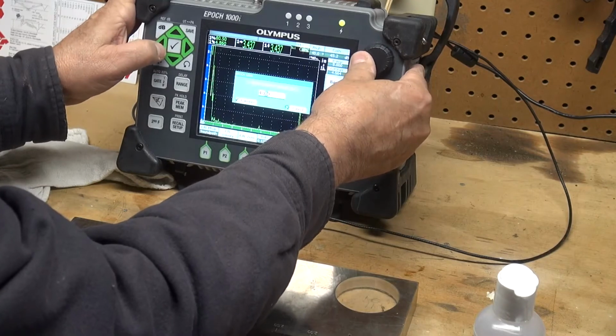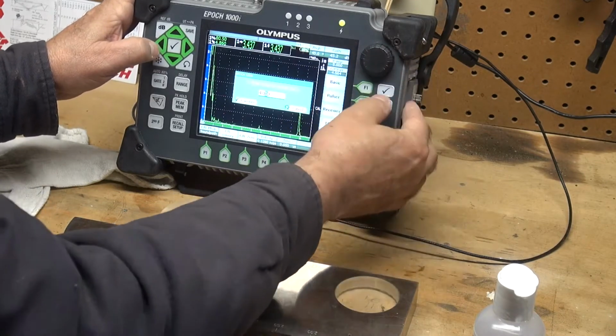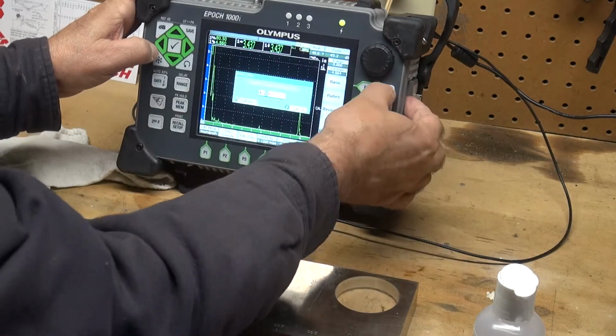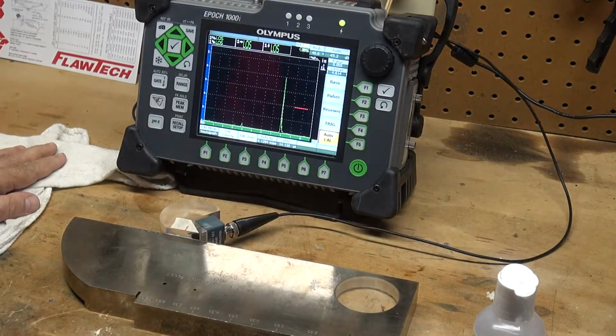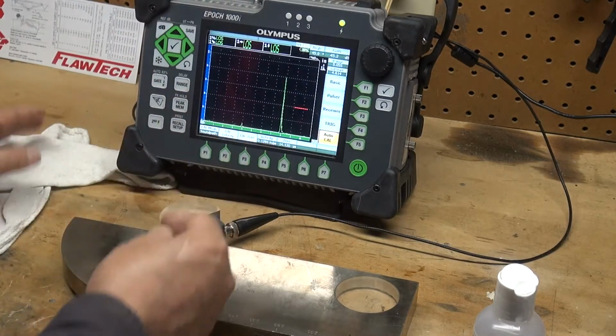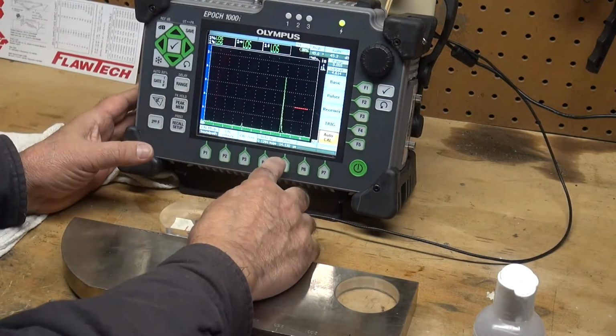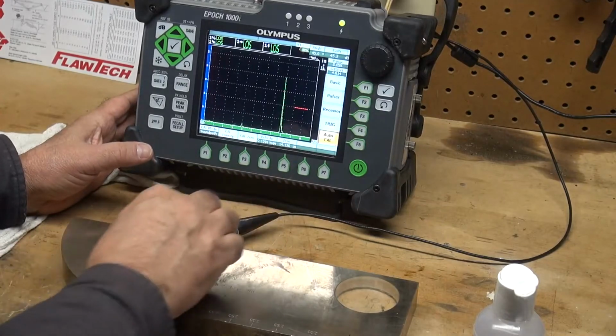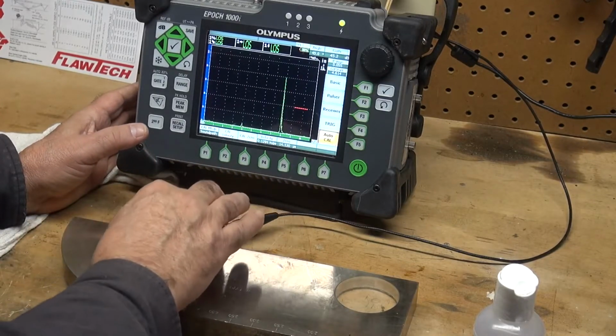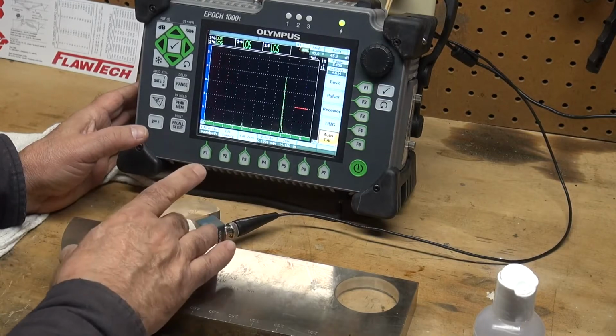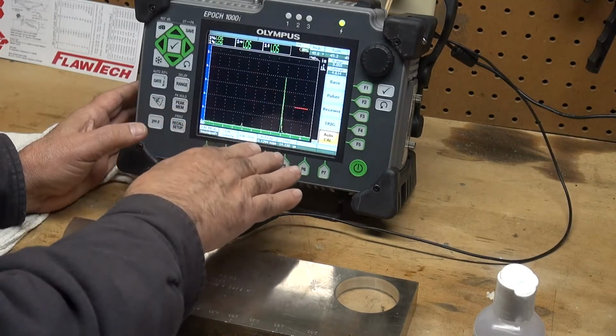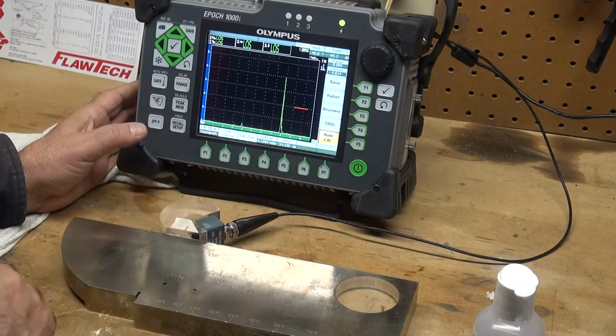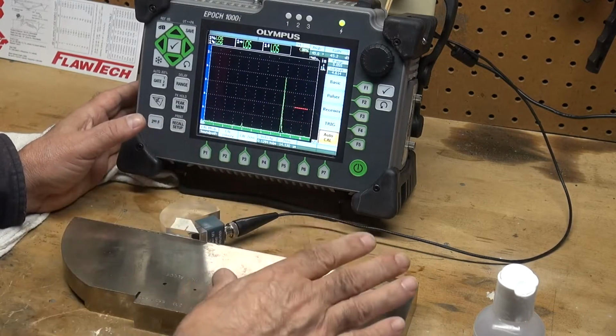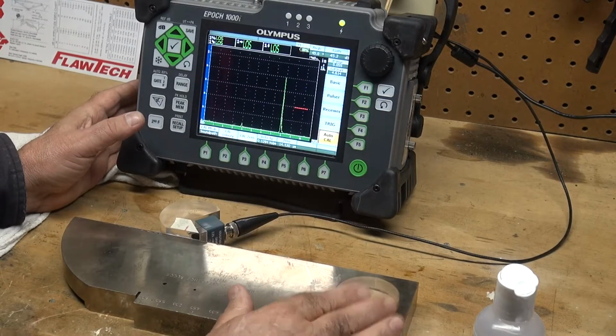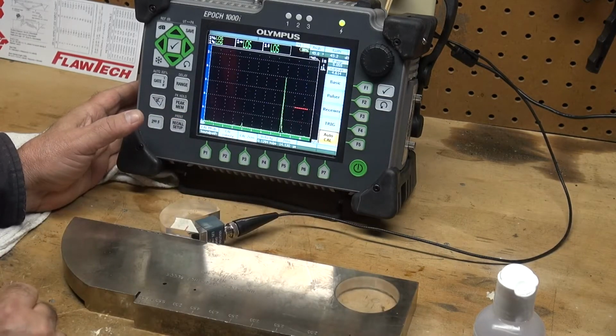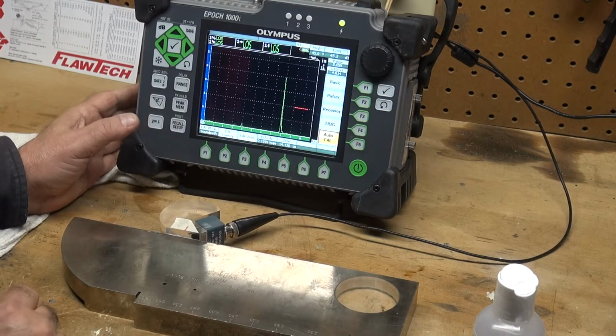So I'll adjust this to 4 inches, and then the check mark will calculate my calibration and complete the calibration. In this case, the 0 is 14.12 microseconds. That's how much time is spent in the wedge. It doesn't take into account the steel. We don't want to have the wasted time in our calculation. And for this IIW reference block, it changed the velocity from 0.128 to 0.129 inches per microsecond.